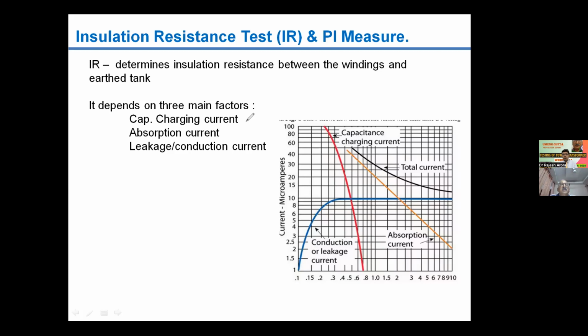when we do this test, the current which flows through the insulation will have three components: capacitive charging current, then absorption current, which is also known as the ionization current, meaning the molecules take polar form. So this current is also known as the polarization current or absorption current, and the last current is the leakage or conduction current.